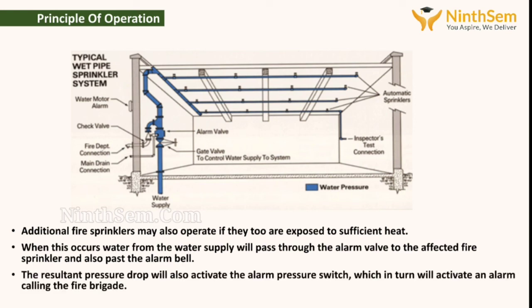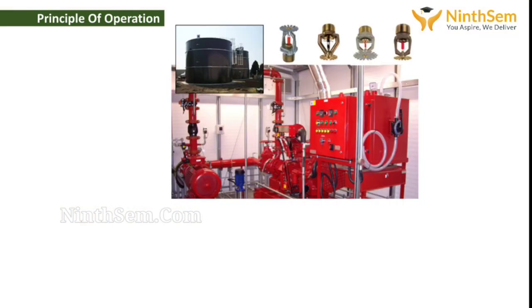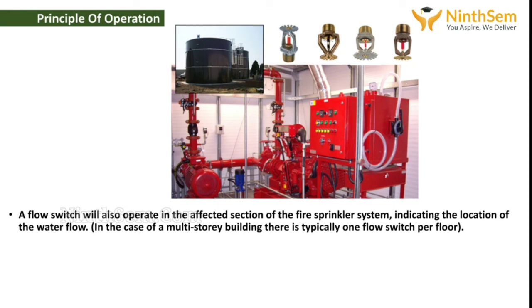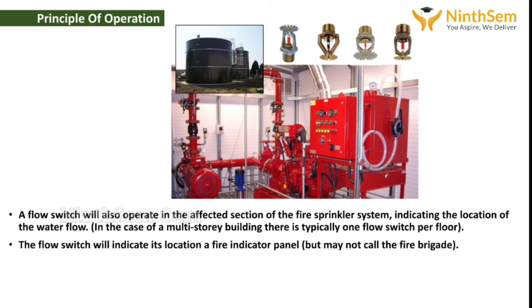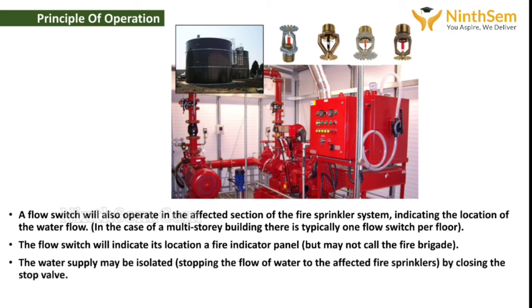The resultant pressure drop will also activate the alarm pressure switch, which in turn will activate an alarm calling the brigade. But in India we are not arranging such kind of arrangement. But abroad they are using such kind of arrangement. So a flow switch will also operate in the affected section of the fire sprinkler system, indicating the location of water flow. In the case of a multi-story building, there is typically one flow switch per floor, and the flow switch will indicate its location at a fire indicator panel on the ground floor. The water supply may be isolated, stopping the flow of water to the affected fire sprinkler, by closing the stop valve.